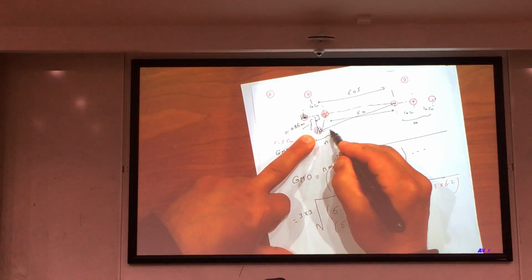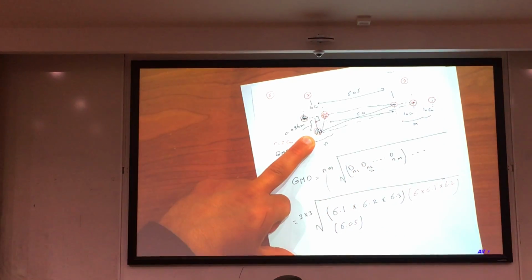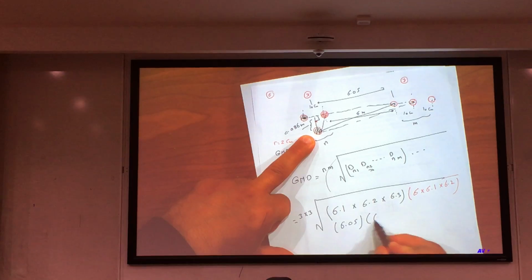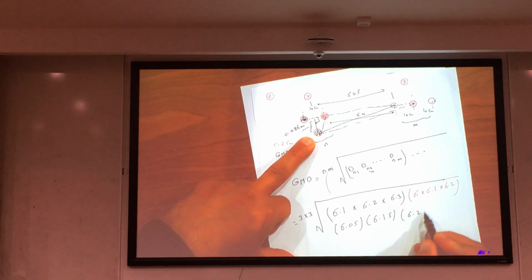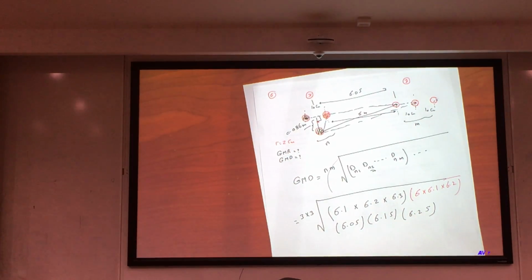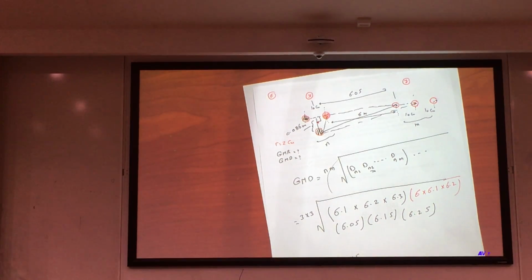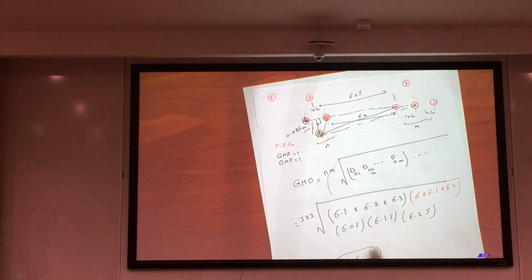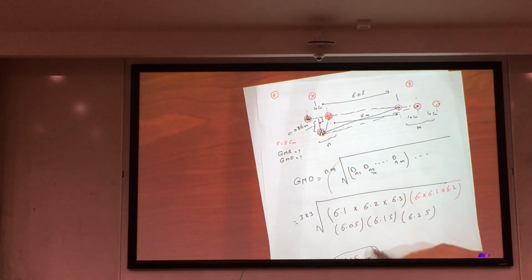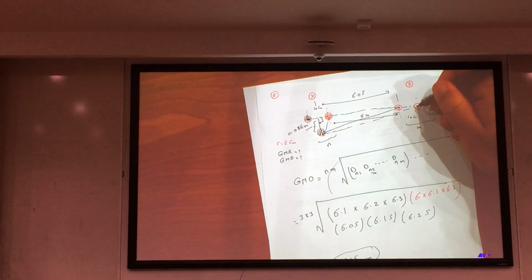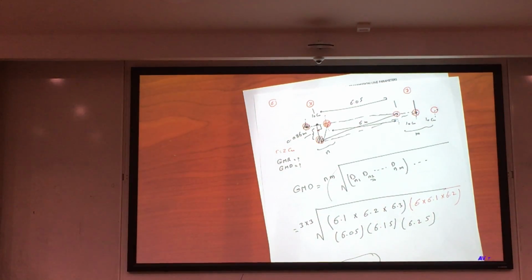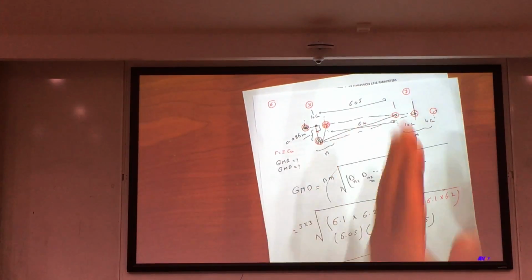Again, calculate the distance between this one and second one. From the big triangle, it will be around 6.15. And the distance between this one and the third one will be 6.25. What you will get here, you will get the answer is 6.15 meters, which actually is almost the distance between the center of the conductors in Y side and this point here, because the distances here are very small. So if you don't want to spend time on this, you can approximate your solution and say that I will take the distance between the center of this side, which is easy here to identify.